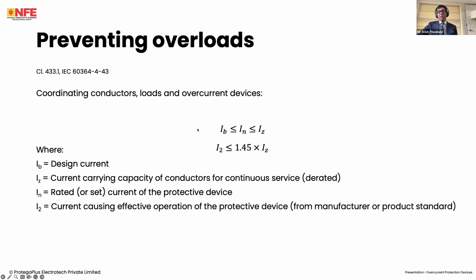That's quite an interesting thing, because we look at IB and we look at IT really, which is the tabulated value. We don't even derate. We know how to select a cable for a given design current, but we forget about the actual overload protective device. So that's an important consideration. Say if my design current was 100 amps, I would choose a device that had a value less than or equal to this, so say 100 amps again. And the cable should be able to carry, after derating, more than 100 amps.